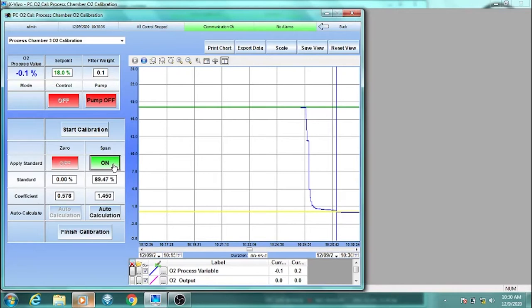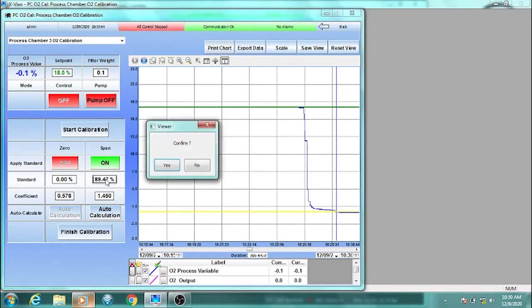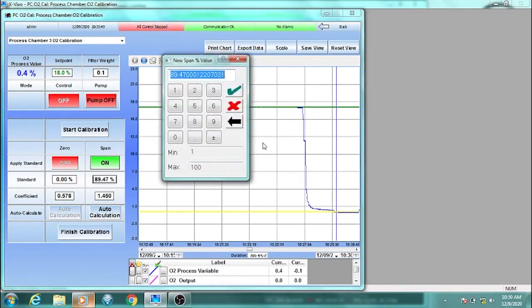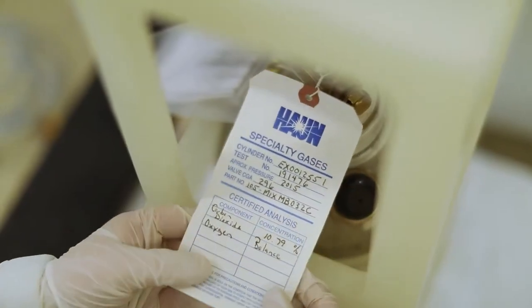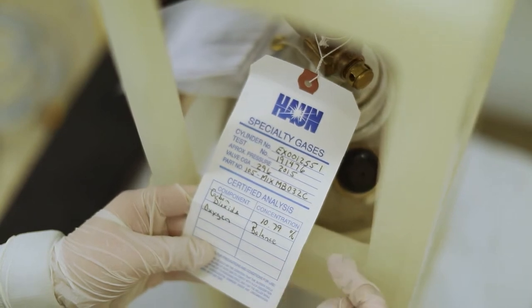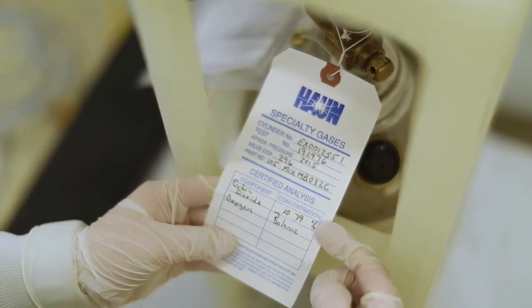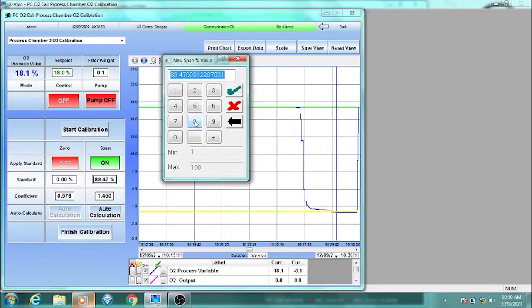Next, turn on the span calibration. Check the standard and make sure it matches the concentration of the span tank you are using. If it does not, click the standard and it will ask you to confirm. Click Yes. Input the correct value for the span tank. As you may recall from the beginning of this video, the tag on the tank said it contained 10.79% carbon dioxide, and the rest is oxygen. Therefore, the oxygen in this tank is 89.21%. Type this in and confirm with the green check mark. This will update your standard for the span gas.